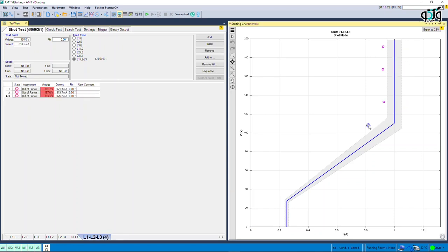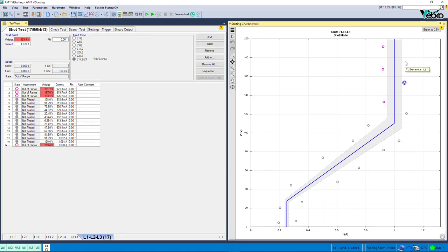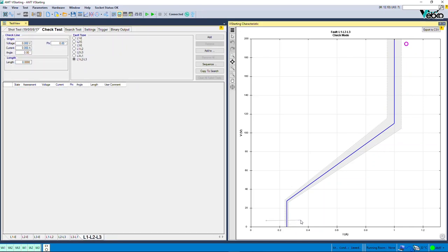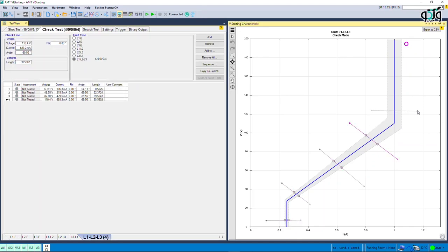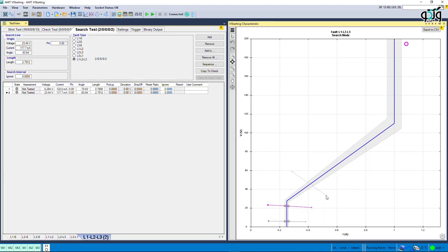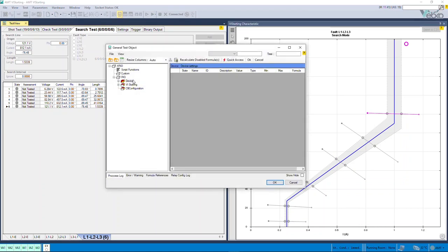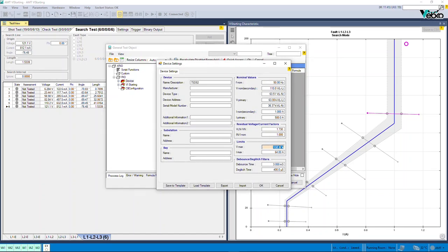Note that the plotted check line should cross at least one of the tolerance lines of the characteristic curve. The search test is the last test performed on the VI starting characteristic curve. The purpose of this test is to find the characteristic curve line. The search line method is the same as the check line. By performing the test, the software tests several points on the search line, interpolating the characteristic curve and determining its exact location. Keep in mind that due to the required voltage level, by referring to the test object parameters and then the device block, the final voltage limit or Vmax may need to be increased.